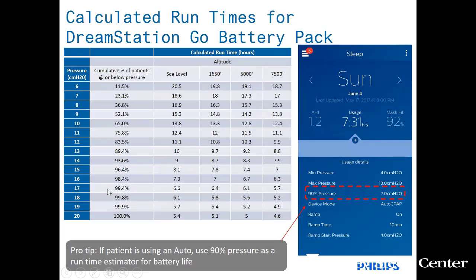If you look here, the percentile of people who are going to be under 13 centimeters of pressure is almost 90%. So as you get up to the four highest settings, 17, 18, 19, 20, that's less than 1% of CPAP users. So really, if you look at the sea level hours, you can get 8 hours out of one charge if you're on a pressure of 15 or below. And of course, if you go way down in pressure, you can get up to 20. So you can get a lot of battery life out of this. I think if you're in the 1% who is 17 or higher, the battery might not be for you because you're only going to get 5 to 6 hours out of it there.